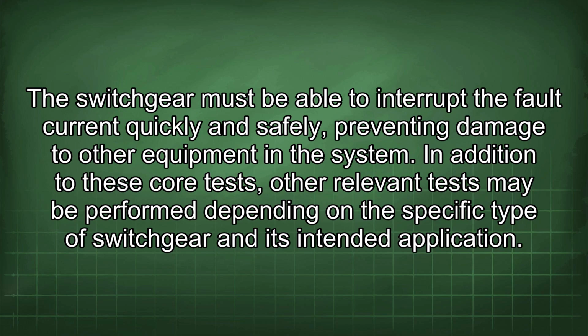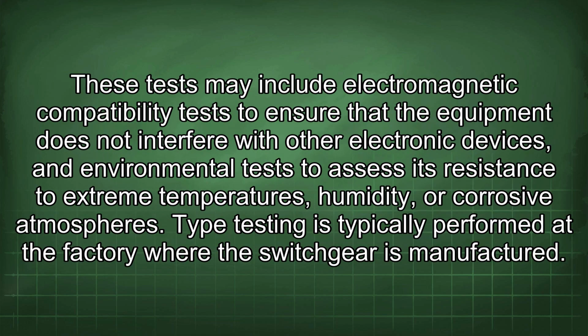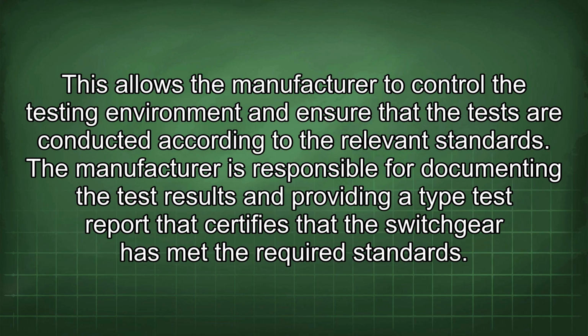In addition to these core tests, other relevant tests may be performed depending on the specific type of switchgear and its intended application. These tests may include electromagnetic compatibility tests to ensure that the equipment does not interfere with other electronic devices, and environmental tests to assess its resistance to extreme temperatures, humidity, or corrosive atmospheres. Type testing is typically performed at the factory where the switchgear is manufactured. This allows the manufacturer to control the testing environment and ensure that the tests are conducted according to the relevant standards. The manufacturer is responsible for documenting the test results and providing a type test report that certifies that the switchgear has met the required standards.